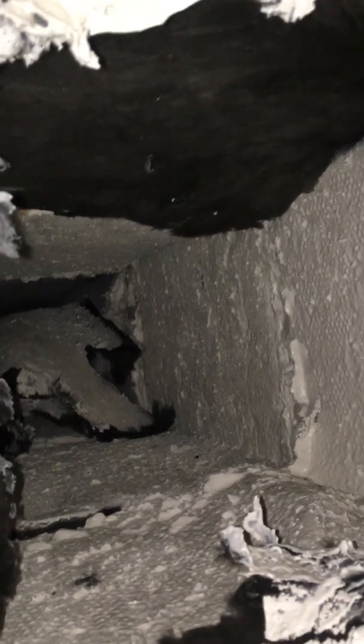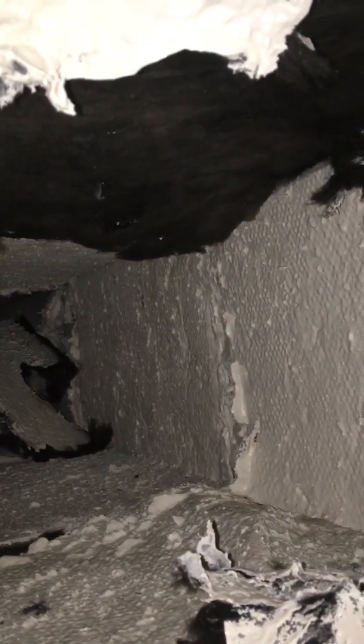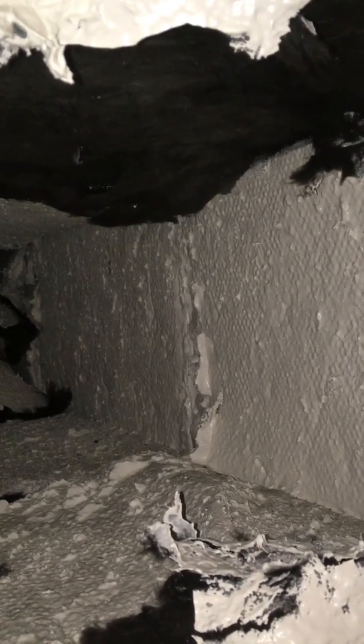The insulation, this internal insulation in this duct, which was fabricated in the late 1980s and has a design life of 20 years, was originally yellow. It's blackened, because it's full of mold. It's fiberglass insulation. Fiberglass is a lung irritant, and mold is unhealthy to breathe.